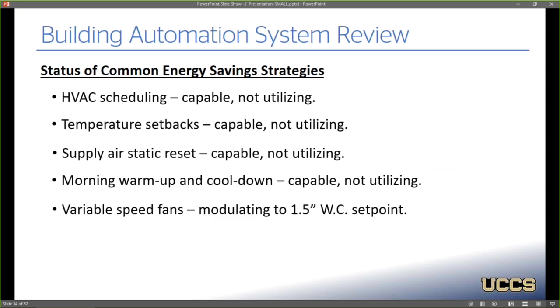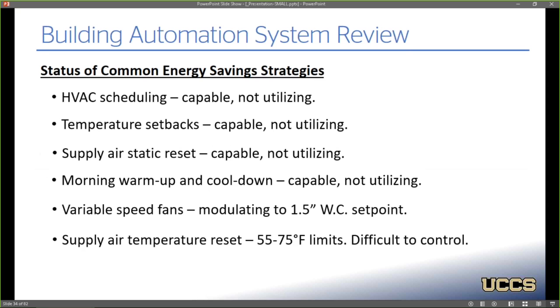The office supply fans are variable speed. They're modulating to a 1.5-inch water column set point, and the supply air is being reset between 55 and 75 degree limits. But due to the limited staging on the heating and cooling, it's extremely difficult for them to actually achieve the set point that they want, especially in heating mode when the fan goes to a low speed condition and now you turn on one stage of heat and you get a 20-25 degree temperature rise and they overshoot their set point, and then it turns off and now you're under. So there's a lot of cycling of equipment.